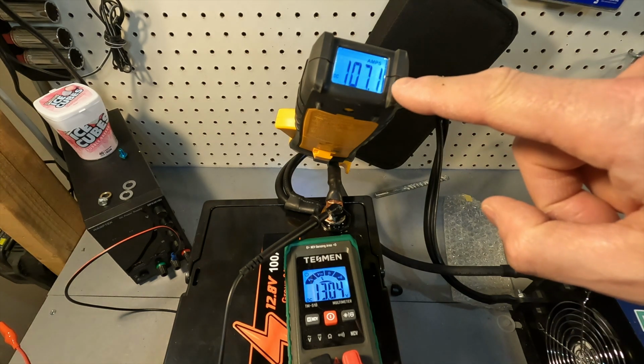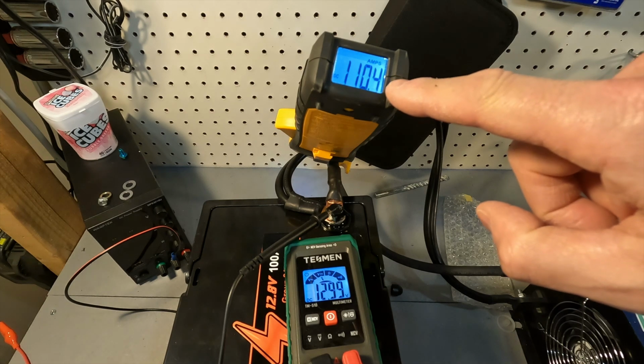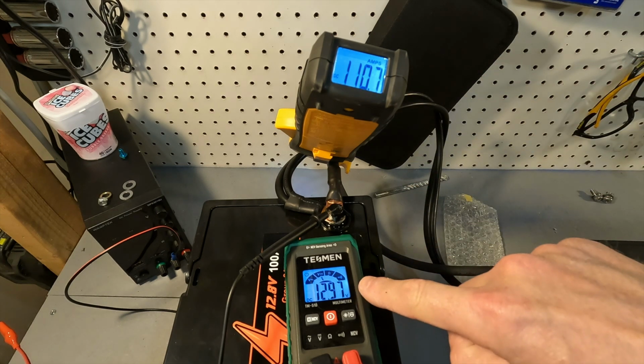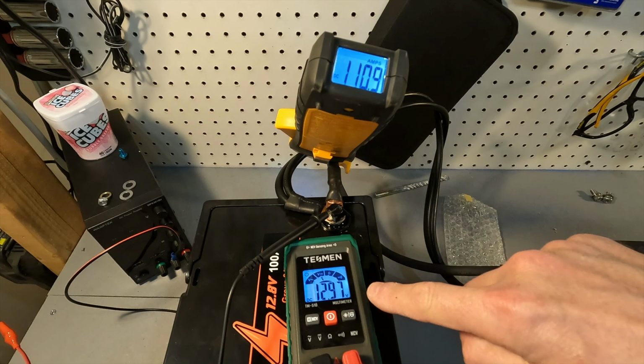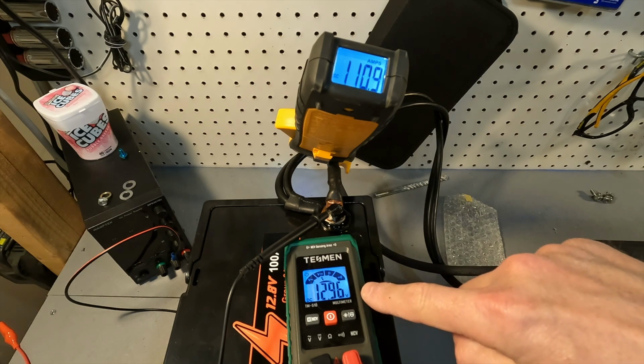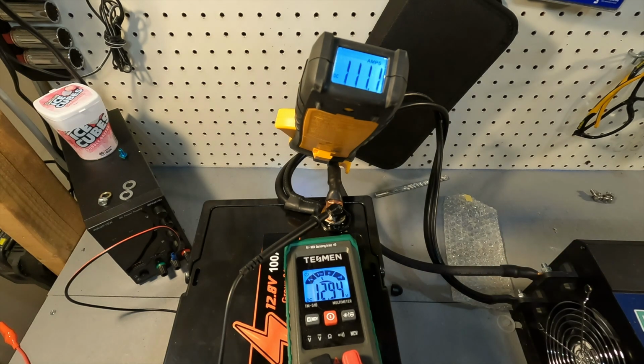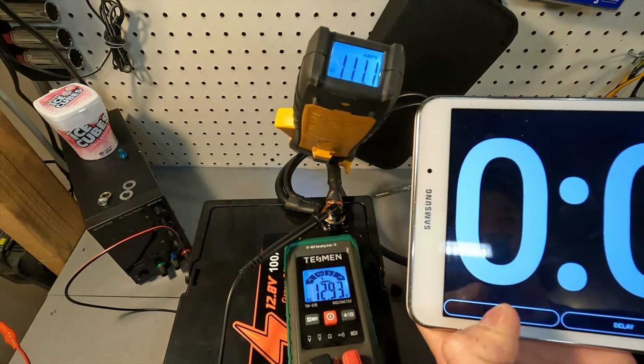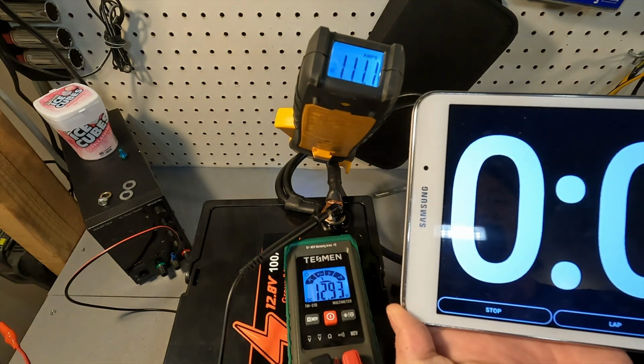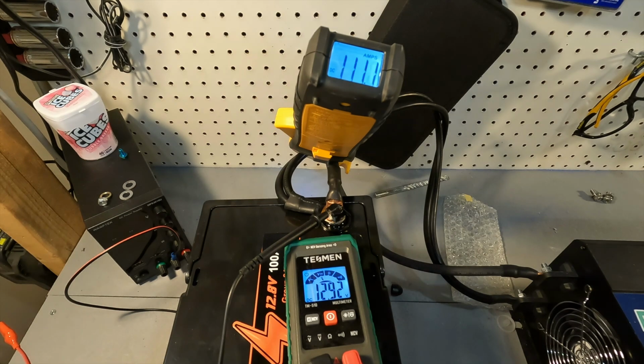All right, our amperage has jumped up over 100, it's now at 110. Our voltage is down to 12.97. We'll see if it holds there. I've also got this timer right here, so we'll go ahead and start it, and we're going to let this run for 5 minutes just to make sure it can handle 111 amps with no problem.